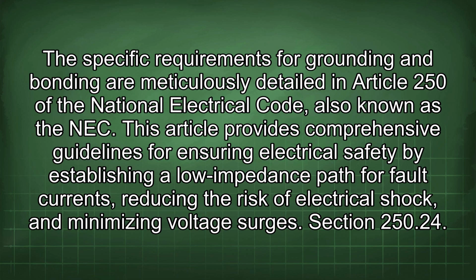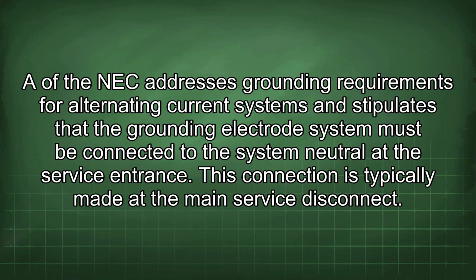Section 250.24 of the NEC addresses grounding requirements for alternating current systems and stipulates that the grounding electrode system must be connected to the system neutral at the service entrance. This connection is typically made at the main service disconnect.